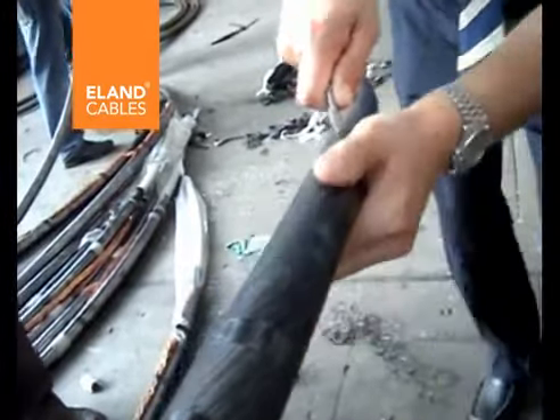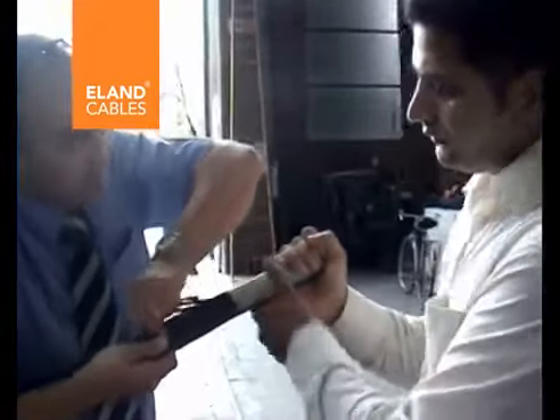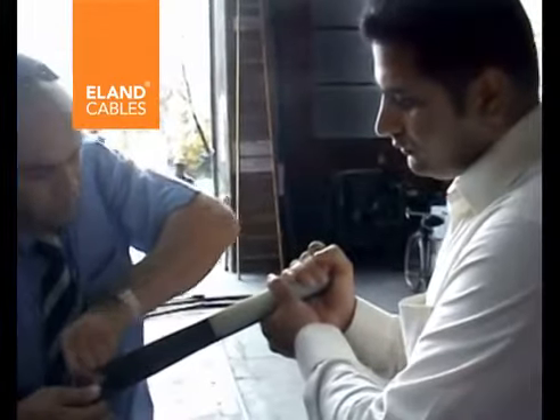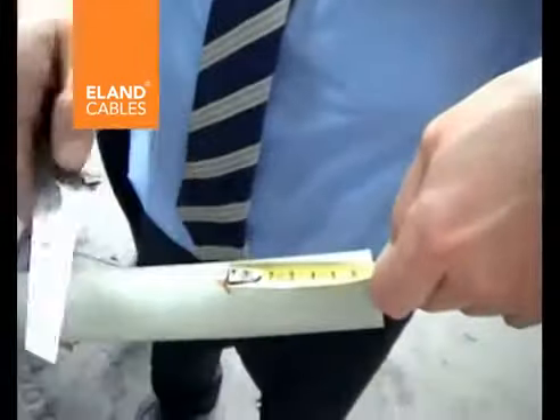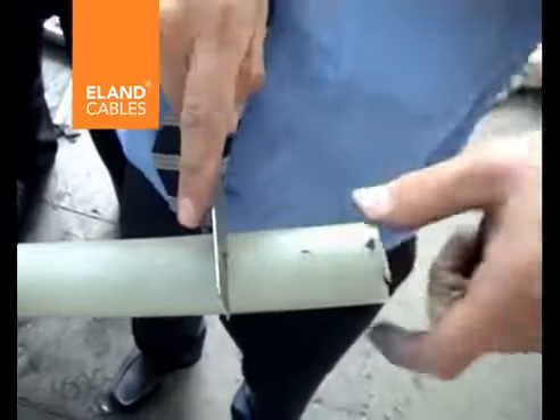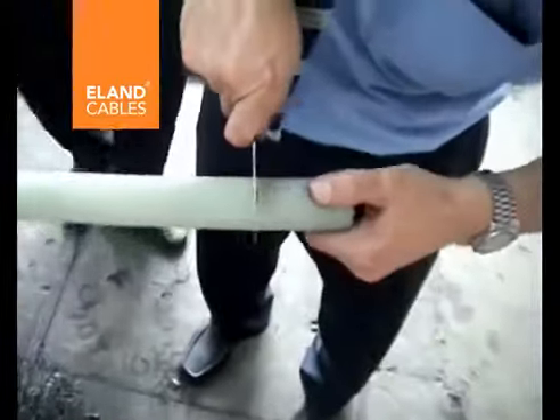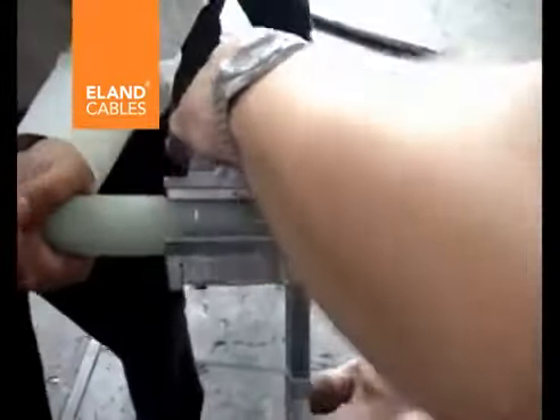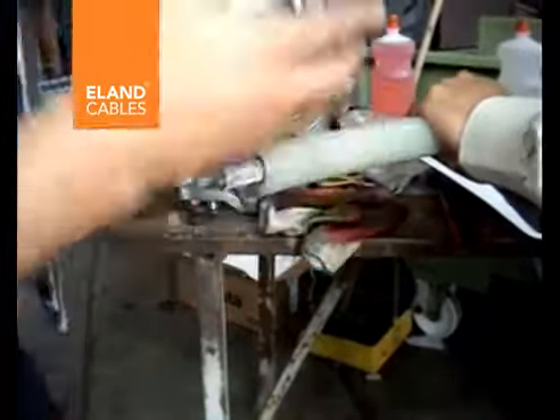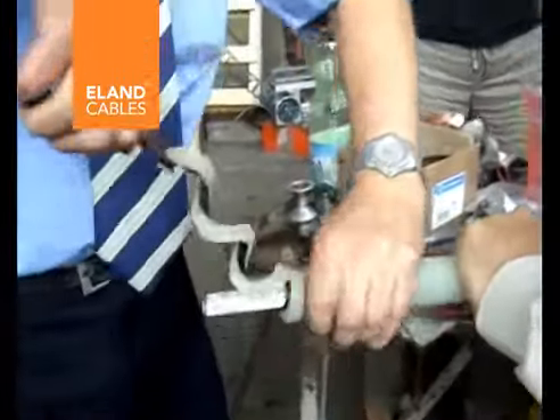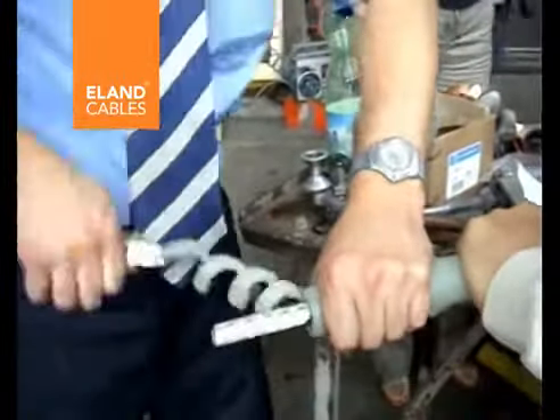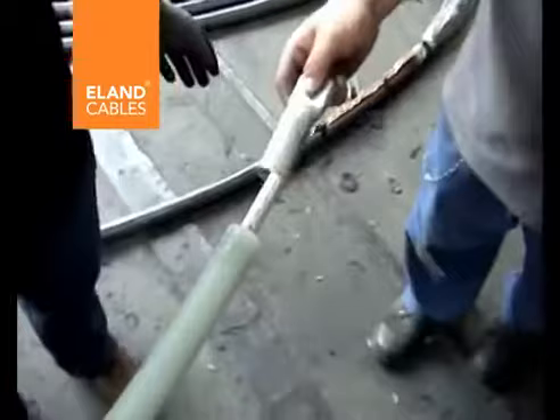This was verified as banana strippable by the Network Rail test witness and by another client. The insulation was then exposed, the end of which was carefully measured to the required 70 mm. This was then removed by the standard stripping tool used by Network Rail jointers. The insulation and semiconducting screen came off cleanly, finally to expose the conductor.